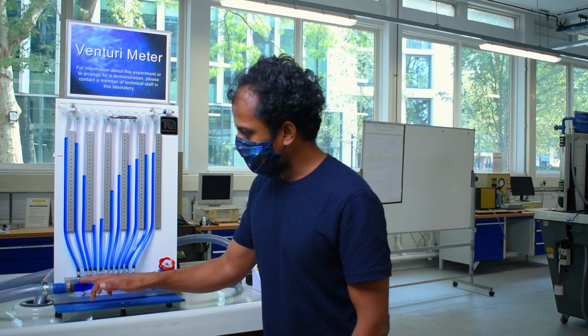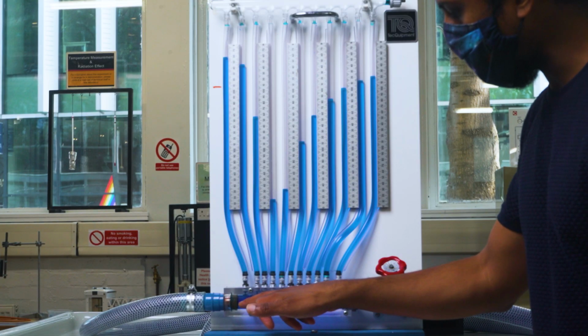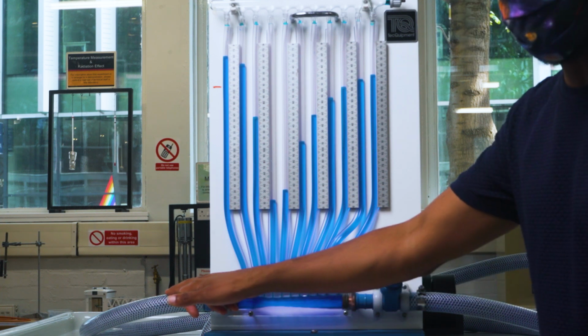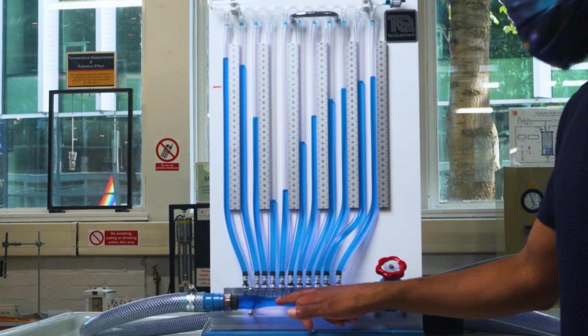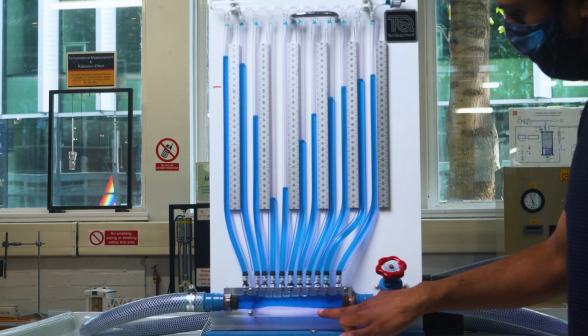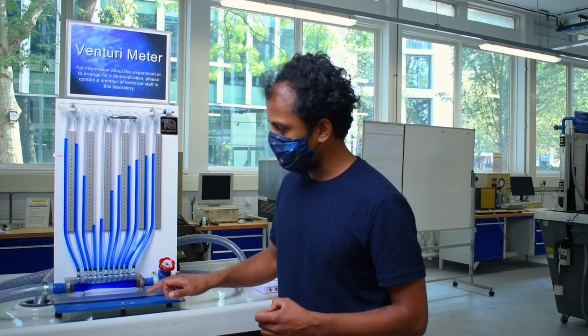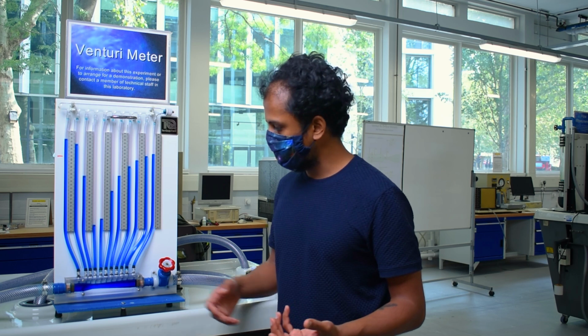So let's remind ourselves about the Venturi meter, what it looks like and what it does. Effectively, at the start here, we have the inlet, which is the same diameter as the pipe. And then it has a sharp decrease in diameter to the throat of the Venturi, and then it slowly, gently increases back in diameter to the original diameter of the pipe. Venturis are used to calculate the discharge in a pipe system. Very useful because there's no moving objects. There's no propeller inside here and digital counter to count that. You know, you could lose the voltage or the propeller could break. In this case, not a lot can break.